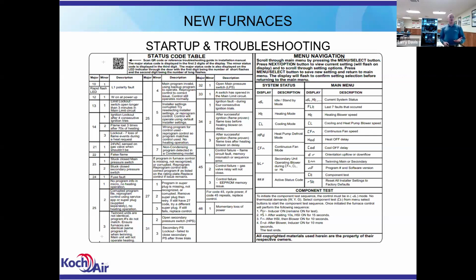Another thing about the faults is, on our previous model furnaces, we just had that blinking light and we had to count the codes. Here we have an LCD display. And also on the previous furnace, what's the first thing you get a call on the weekend? Customer doesn't have any heat. You tell them, go look, and they see the little light flashing through the window on the door.